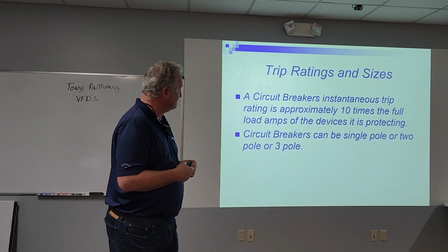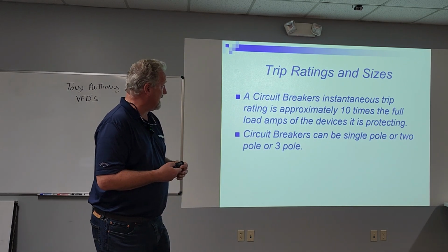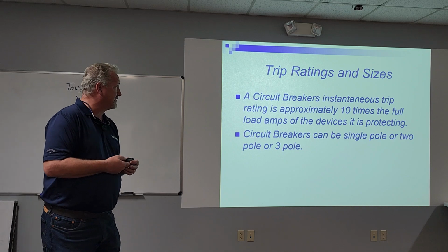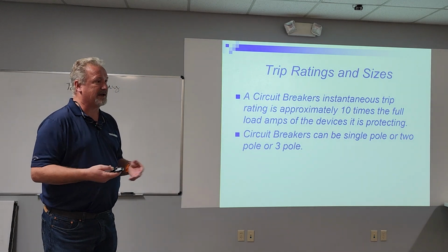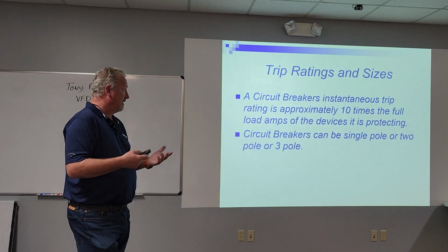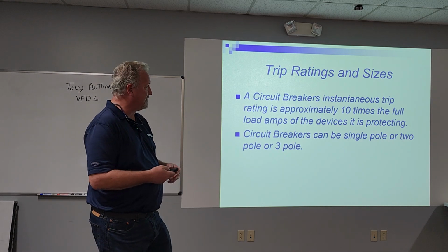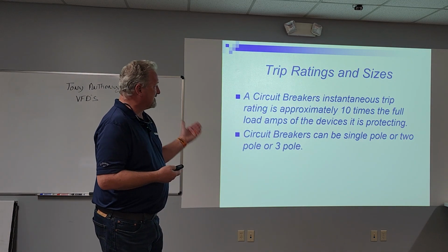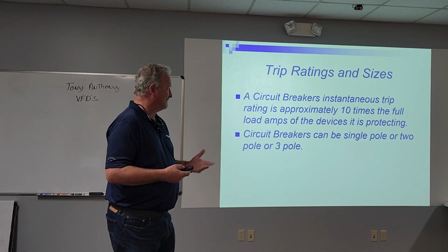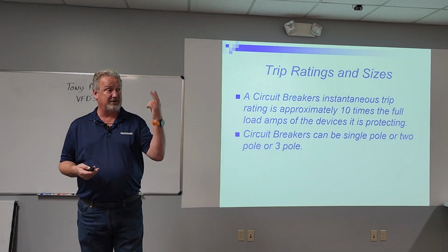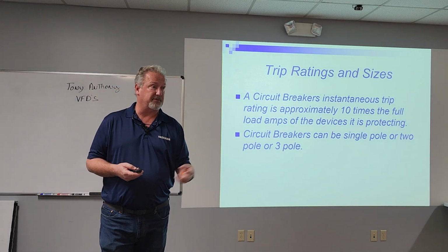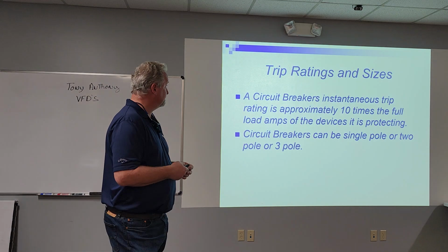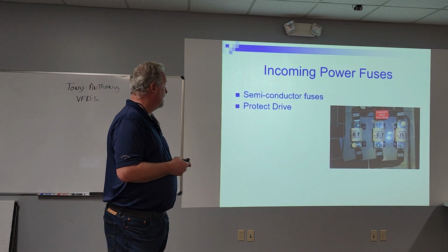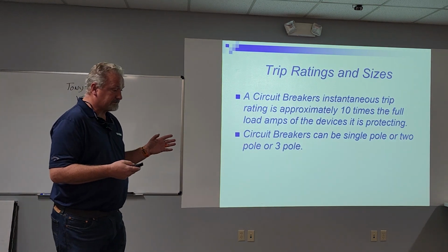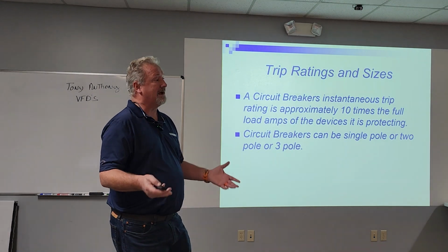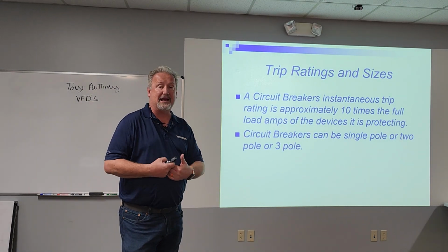Trip ratings and sizes. Most breakers are sized to 10 times the full load amps of the device they're protecting, which is kind of where the common is. That'll give you, if you had the starter at 6 to 8, you can handle it. They can be single pole, 2-pole, or 3-pole. Now, for drives, we don't care about single pole, but we do look at sometimes 2-pole, and then we always have 3-pole. And we'll talk about that here in a second. So that's breakers. That's the most common way we're now protecting drives.